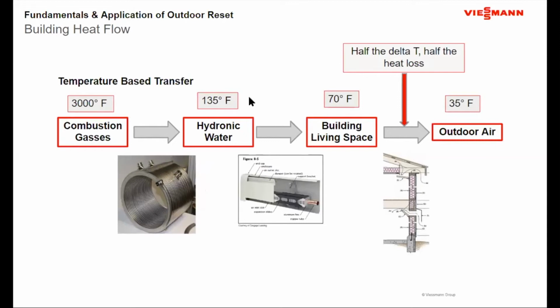All of a sudden, I start to vary the water temperature. Okay, so if the outdoor temperature changes, where it started off at 0 and goes up to 35 degrees, I now have half the heat loss that I did under my design conditions. So if I drop my water temperature from 180 degrees down to 135, my heat emitter now puts out half the amount of heat. Half the amount of heat going into the living space balances with the now reduced by half amount of heat going outdoors, and my living space stays balanced and comfortable.